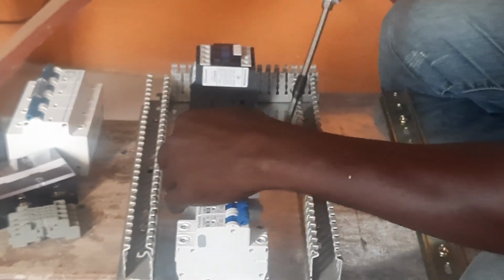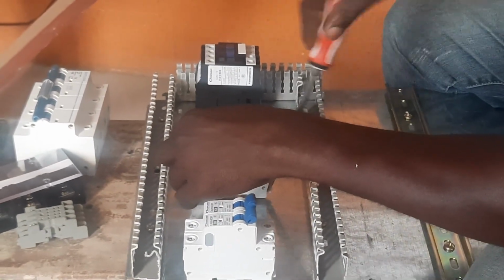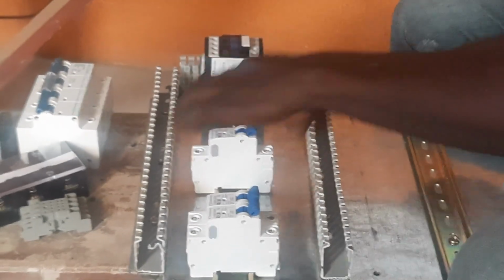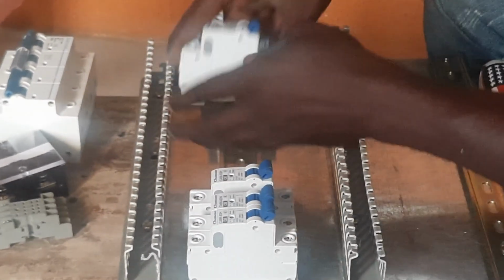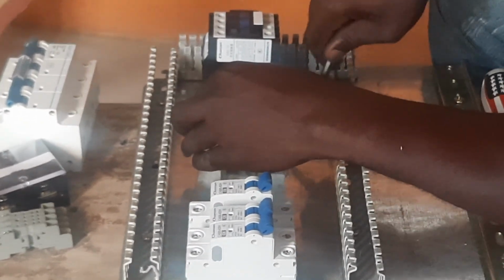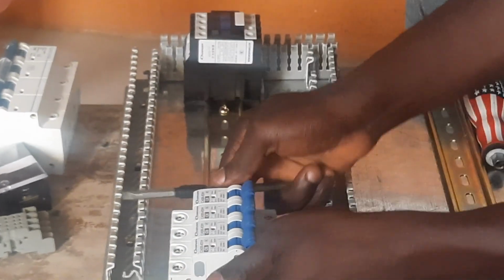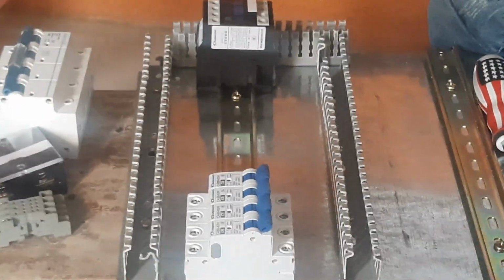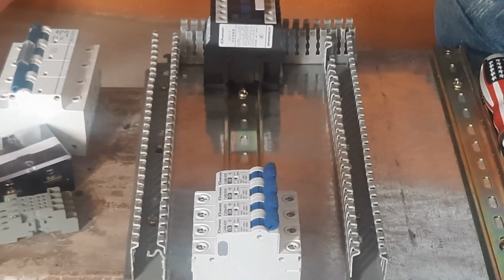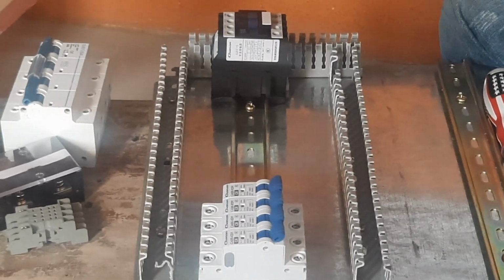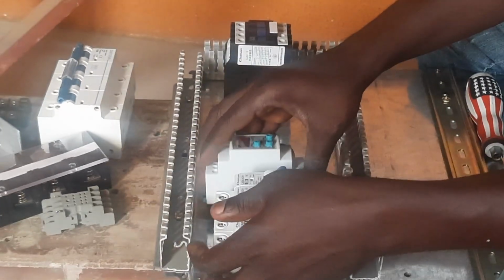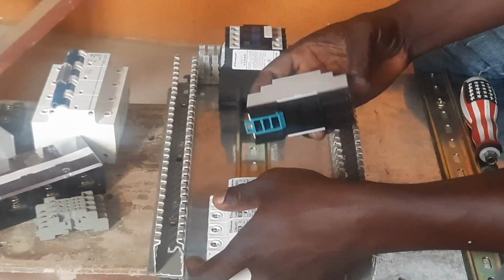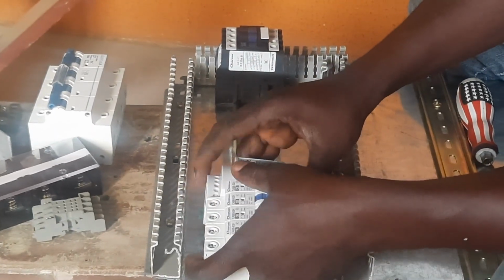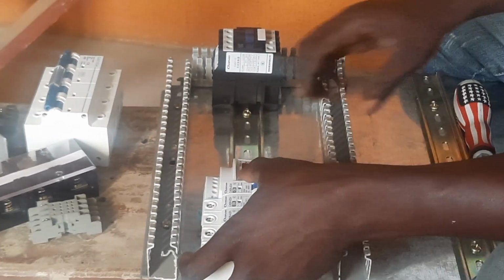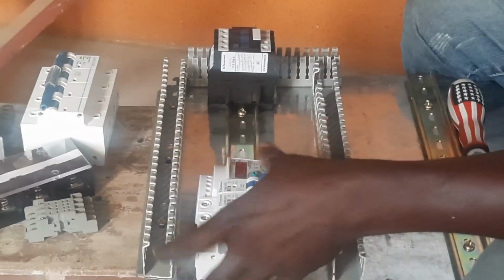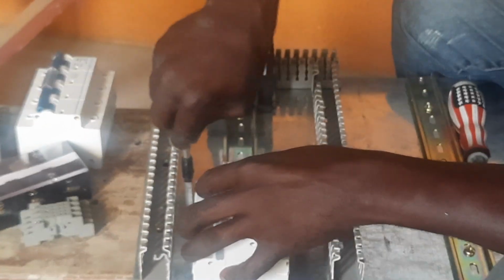A voltage protector to guard against dangerous undervoltage and overvoltage conditions, and of course, three-phase breakers for protection, AC relays for control logic, all neatly mounted on a professional DIN rail. Every single power cable was terminated with a cable lug and shrink tube for perfect, safe connections and clear phase identification. This attention to detail is what separates a professional panel from a DIY project.